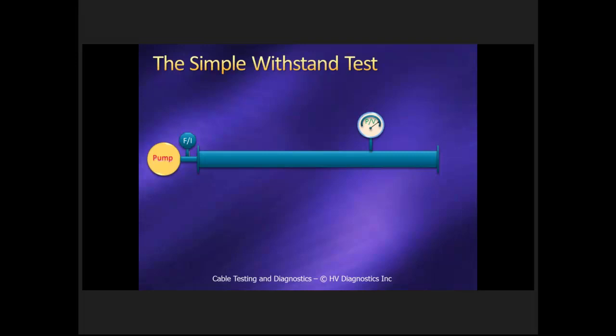So you need to apply voltage whether you like it or not. You can't go into a project and say, I'm going to do a partial discharge test but not energize the cable. You have to have an energization source. If we equate that to hydraulics or a water pump situation, we're feeding from a water pump into a pipe that's been flanged off, in other words, an open-circuited cable.